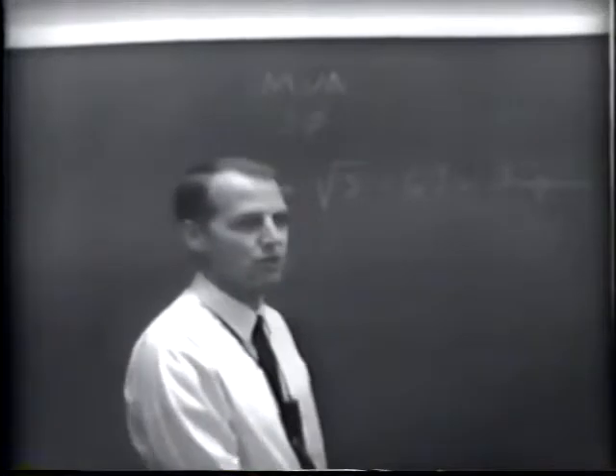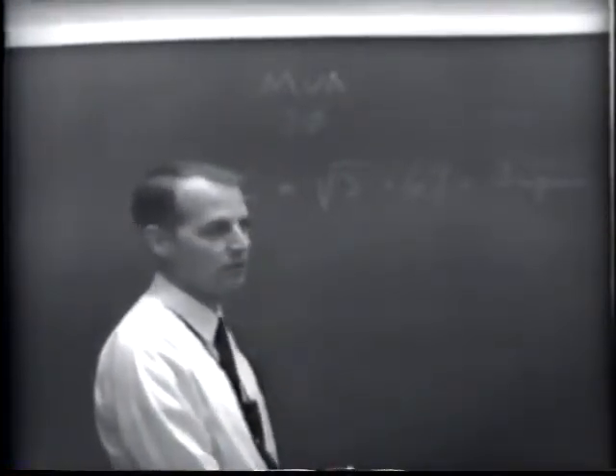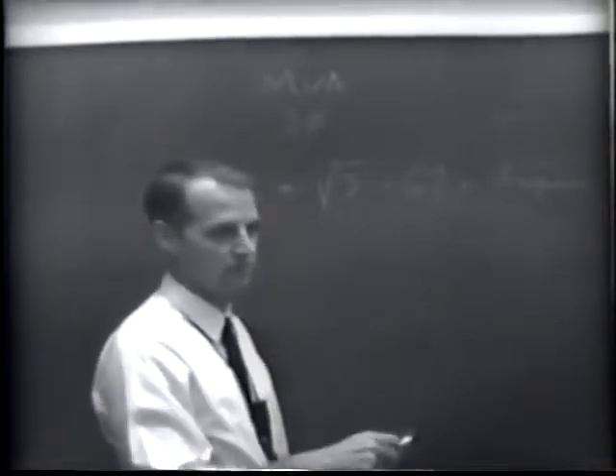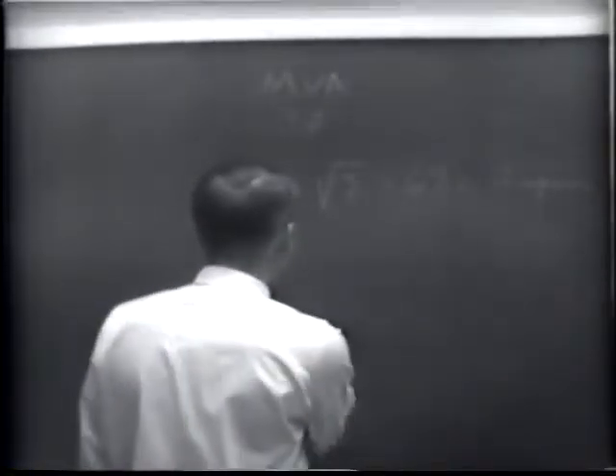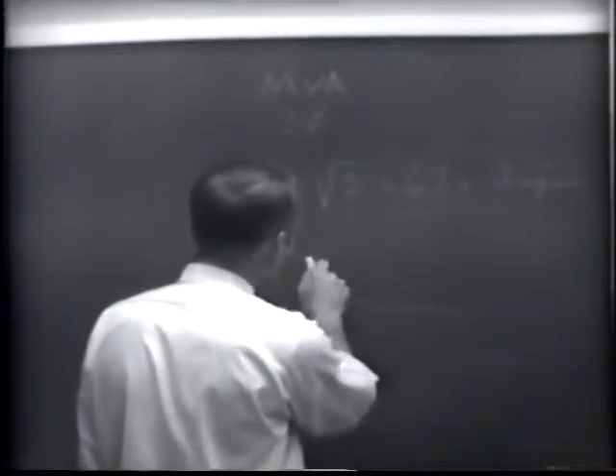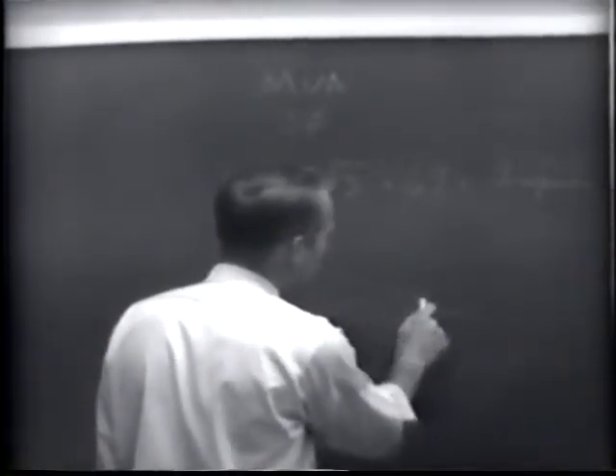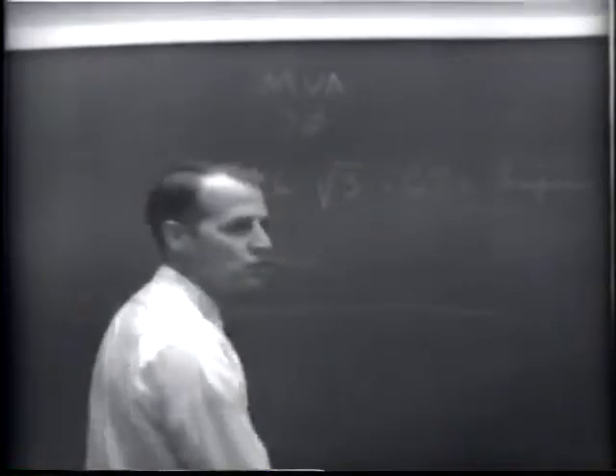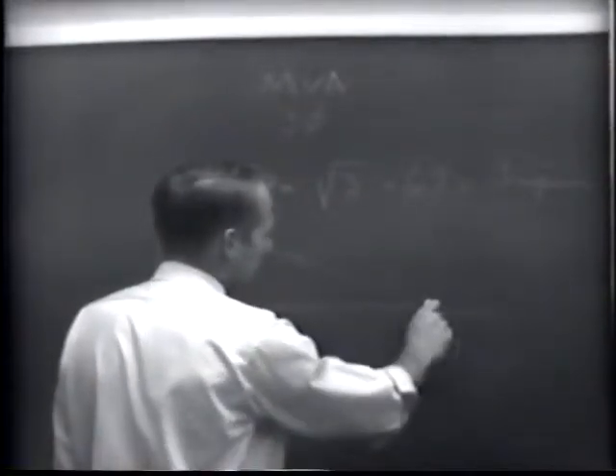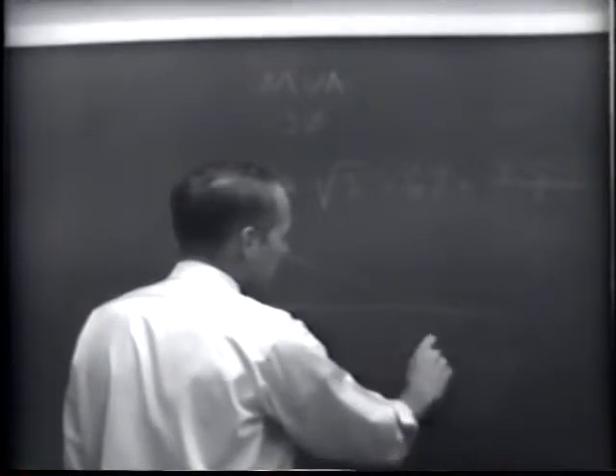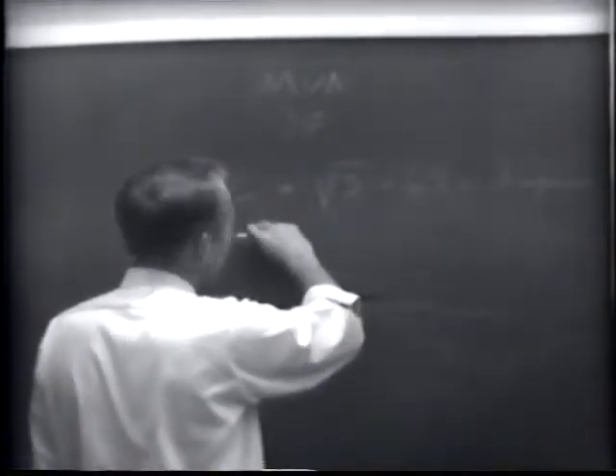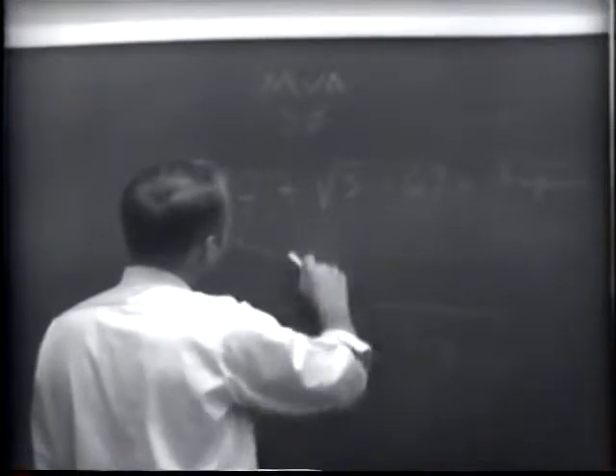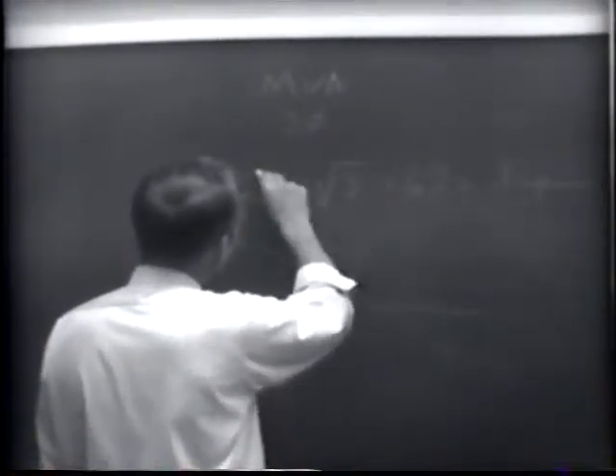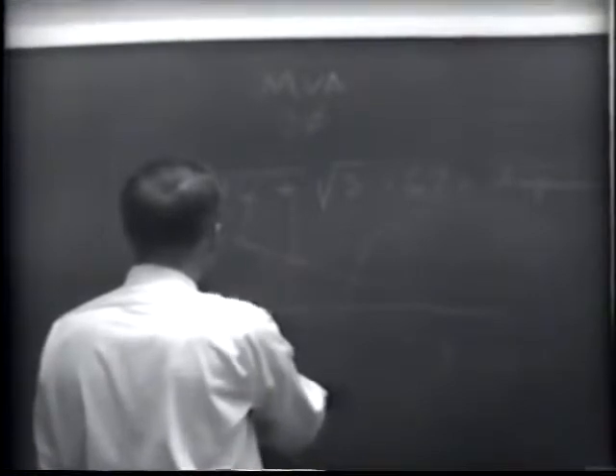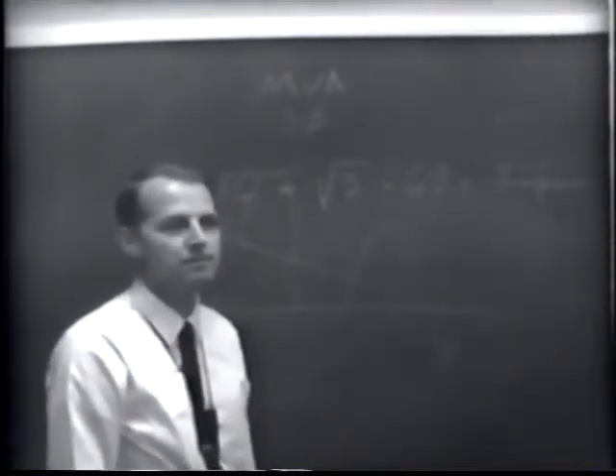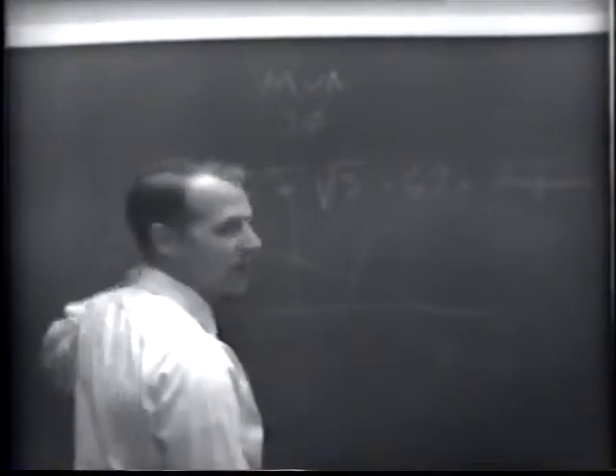So for a very short period of time, a DC current flows with the AC current imposed upon the top of that. So this means that we have a DC current starting out at some value here and decaying very rapidly within a few cycles, probably decaying in 5 cycles at the most. But on top of that, we have the AC fault current. So this means that we have a value of current here that is higher than the actual AC current. Now this is what's called an asymmetrical current.